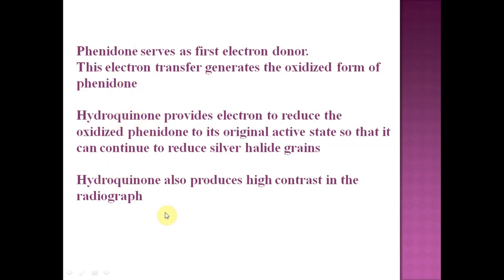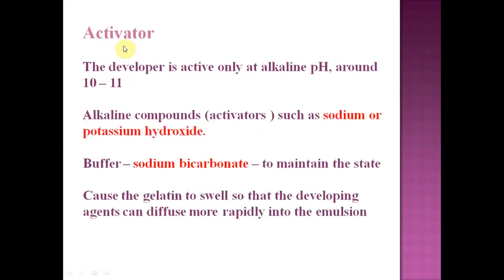Hydroquinone also produces high contrast in the radiograph. The second component of the developer is the activator. The developer is active only at alkaline pH, around 10 to 11. The alkaline compounds used are sodium or potassium hydroxide and sodium bicarbonate buffer to maintain the pH and cause gelatin to swell so that the developing agents can diffuse more rapidly into the emulsion.